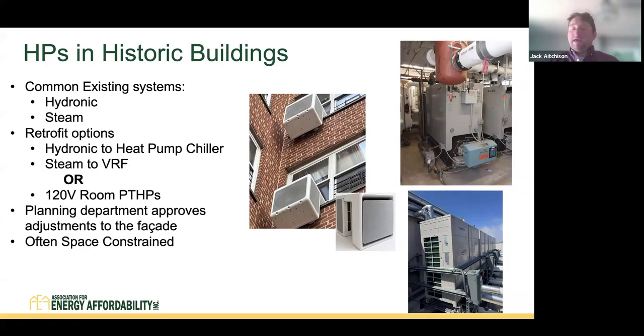Now, what a heat pump chiller does is it operates like a chiller, if you're familiar with a chiller, but it can reverse its cycle and provide hot water to those radiators rather than just cold water. And you can see this here in the photos on the right. This is a gas boiler serving radiators in a multifamily building, and that was pretty much a drop-in replacement with this heat pump chiller. So we were able to remove that gas boiler, put in this heat pump chiller, and keep the same radiators in the unit. Now, of course, there were lots of challenges here because we had to move the heat pump chiller to the roof, so there's some repiping. But in terms of electrification of an old historic building, these are some of the easiest retrofits.